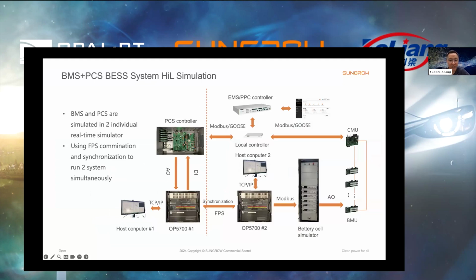Here's another case where we use two simulators running in synchronization. On the right-hand side is our BMS hardware-in-the-loop test system, mainly used to test our BMS - we have BMS controllers connected to our cell models in the real-time simulator. The other side is the PCS controller HIL test platform. We use fiber optics to connect these two real-time simulators and run the whole system simultaneously. In this case, we can simulate thousands of battery cells together with our BMU, our local controller, and the power plant controller, together with our PCS.